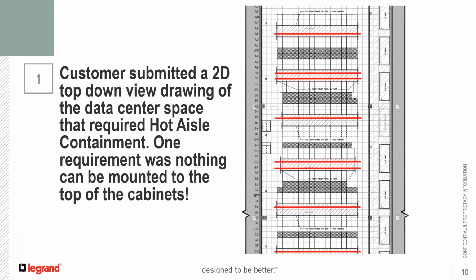In this particular case, we designed it so the customer can roll cabinets into and out of the containment space without modifying or removing the containment from above for their requirement. You typically see this in colo space, where the cabinets themselves are owned by the customer and the containment is owned by the facility. The customer doesn't necessarily want to get facilities permission to remove the cabinets and have to remove the containment.